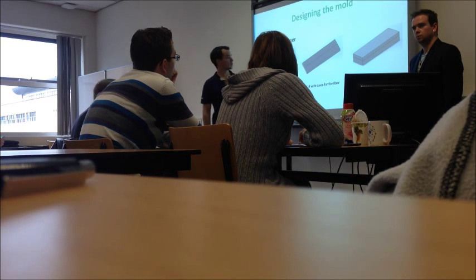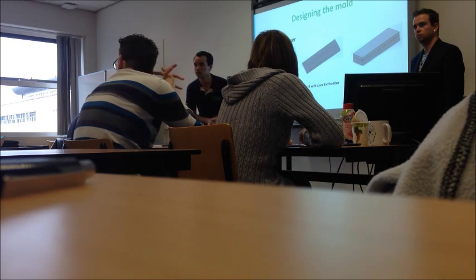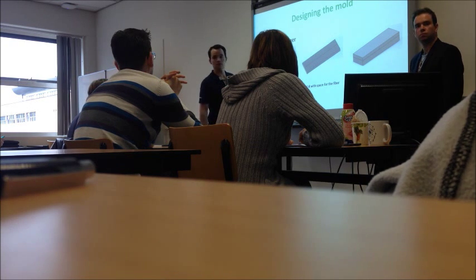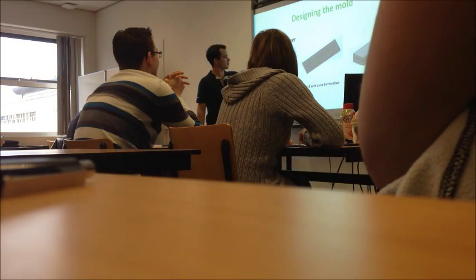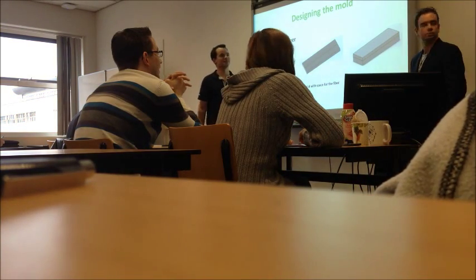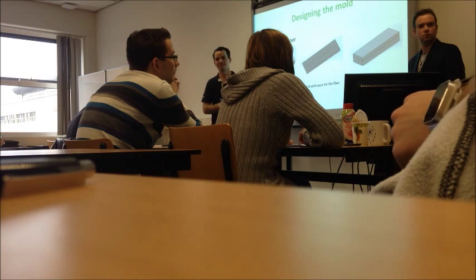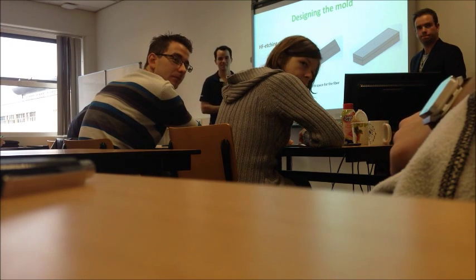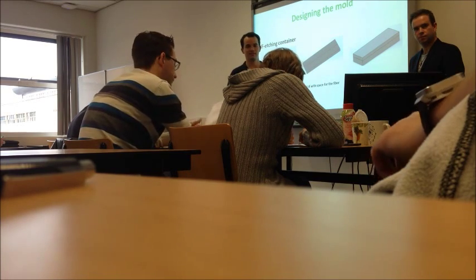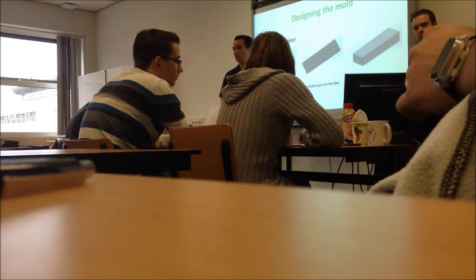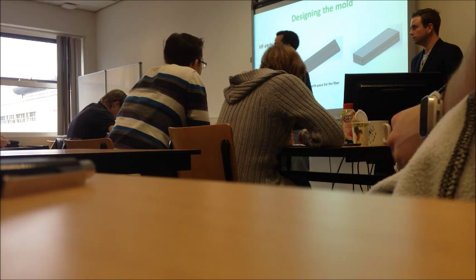The O-ring, what kind of rubber? The rubber O-ring, yes. Is it HF resistant? Yes, the HF resistant O-ring. It's not a rubber, of course. It's a seal. This is the HF and here is the HF resistant. It's another material. I don't know the name. The O-ring is made of Kalrez. It's a special type of rubber, some kind of Viton-like. Okay, are there any other questions?